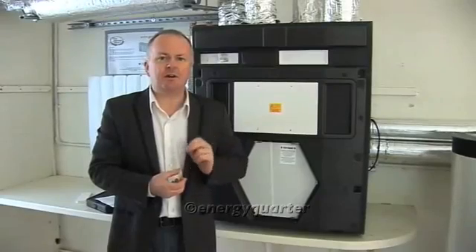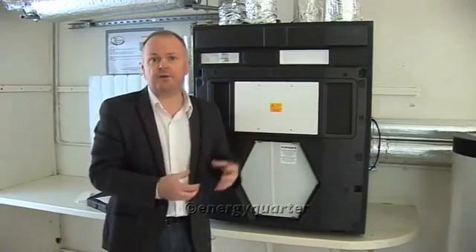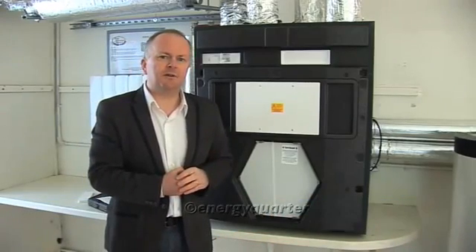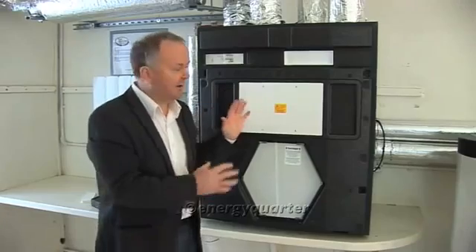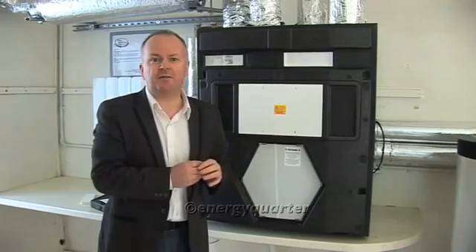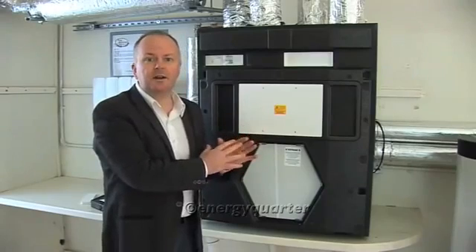The other consideration is electrical consumption — the maximum should be 0.45 watts per cubic meter of air brought into the house. The last issue is noise level. This machine is currently on with the cover off — listen now. I would describe it as a low hum, even quieter than your fridge. Normally this machine sits in your utility room.